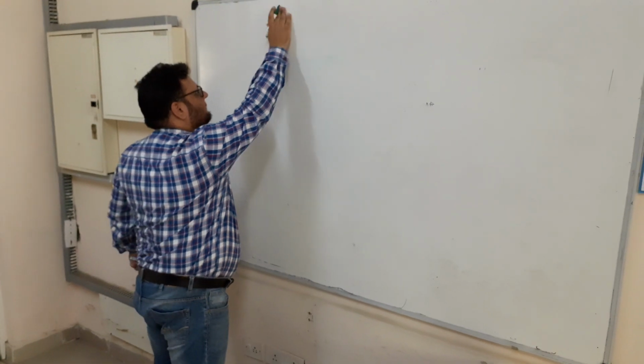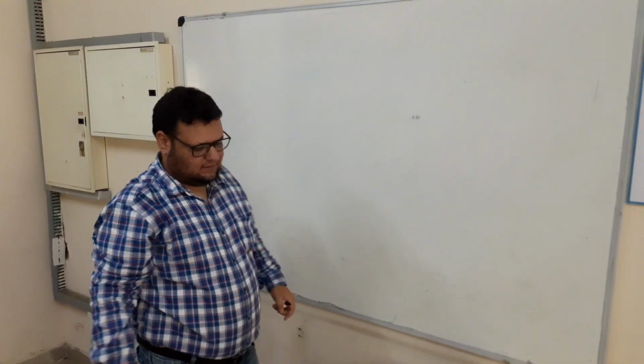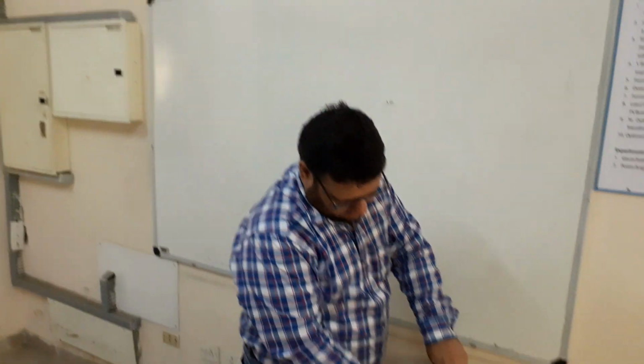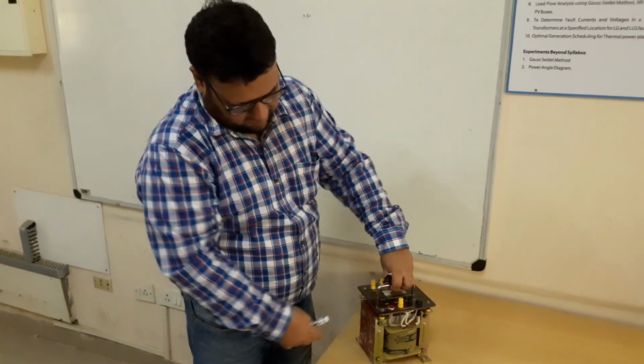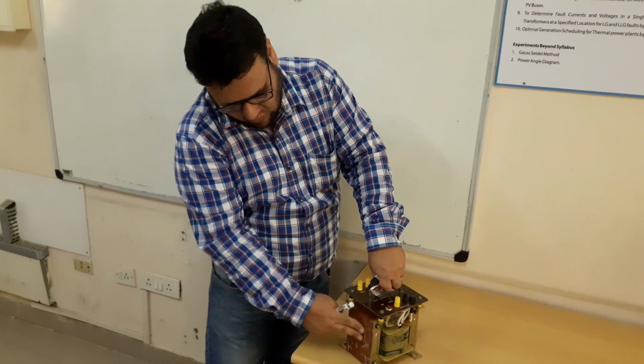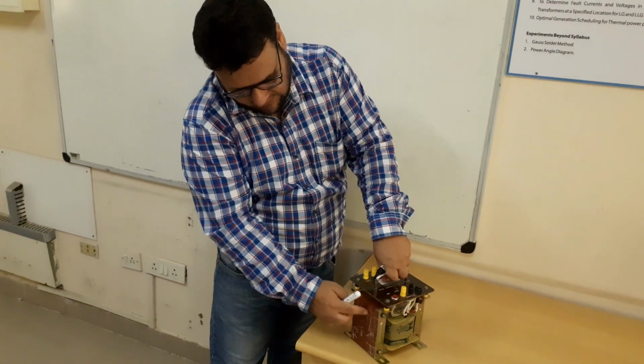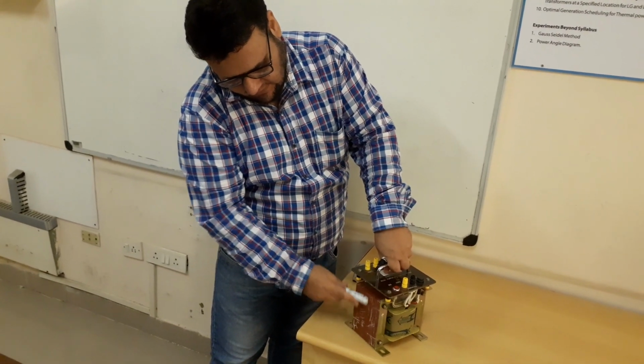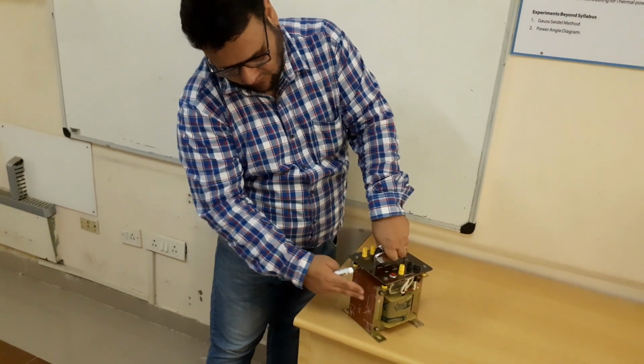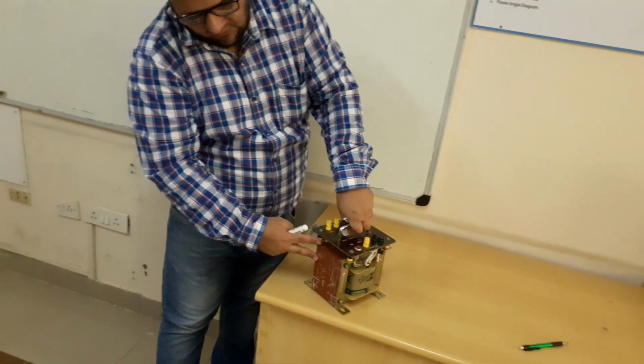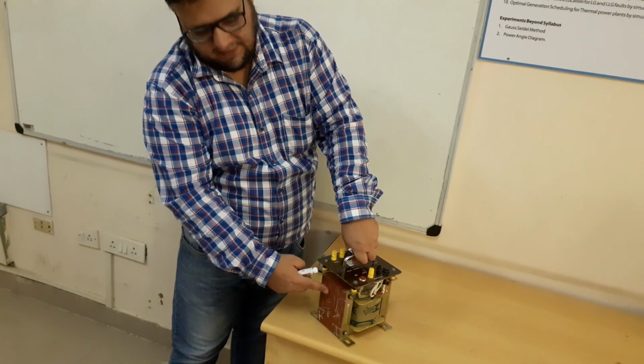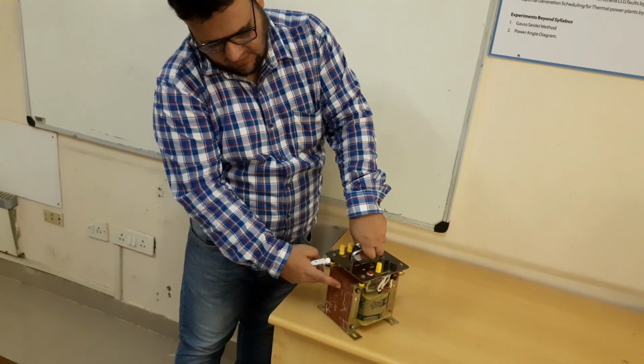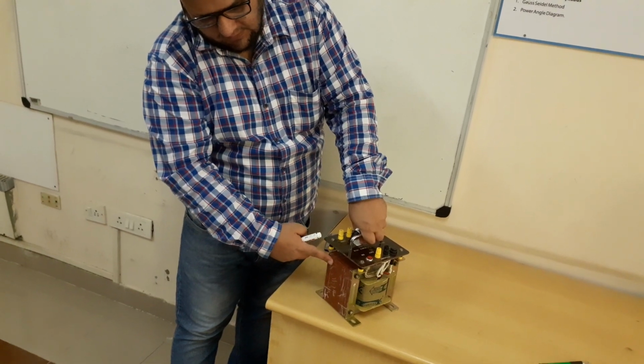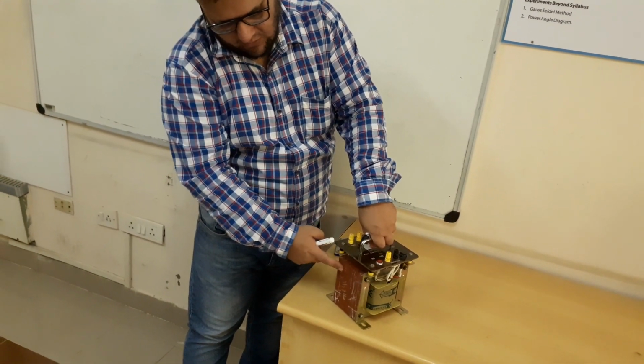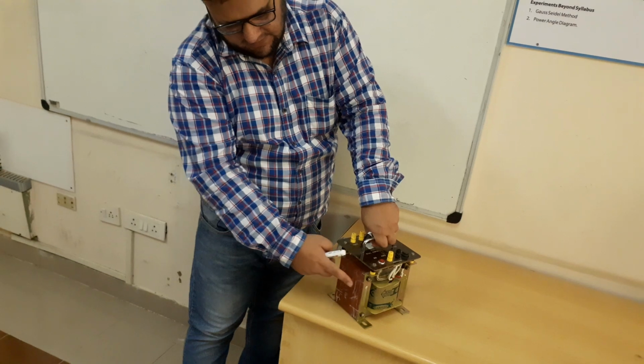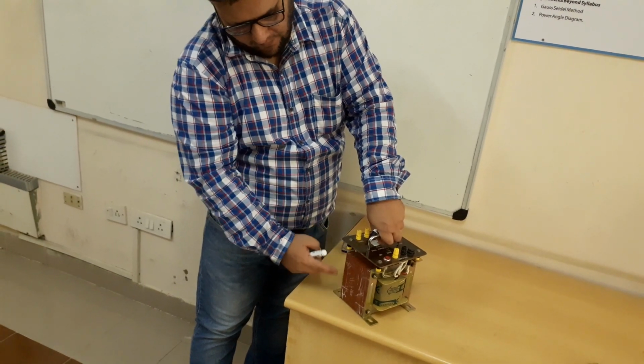The parameters of a transformer are your losses in the winding and the core losses. If you can see this core, this is a laminated core, and the laminations over here are big, and there is a layer of varnish and a coating of silicon applied. This core is made of CRGO, cold rolled grain oriented steel, and this is done to reduce the losses and to make the machine more efficient. And primarily the core is made of CRGO to reduce the core losses.